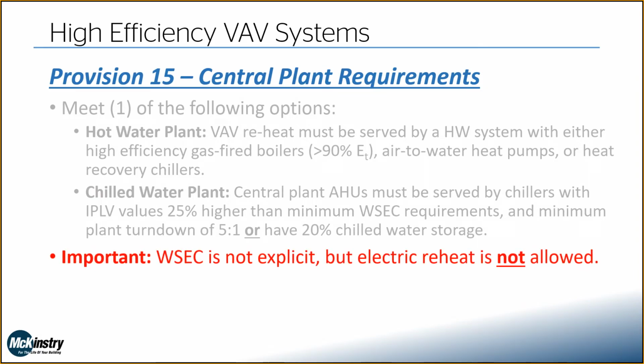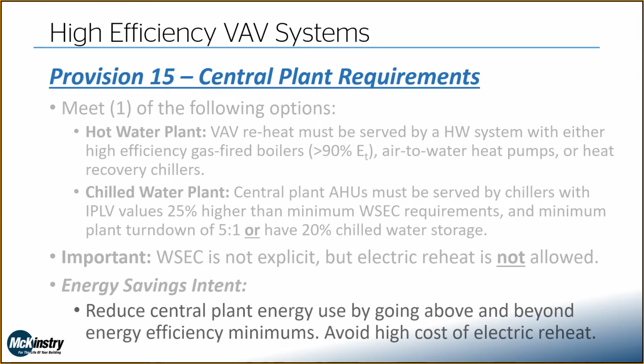An important note here, the code's not explicit, but electric reheat is not allowed. At least this is per the energy code. I forget the team, there's a code technical support team in Seattle, and they say electric reheat does not meet the intent of high efficiency VAV, even though the code is not explicit about that. And that makes sense. I mean, electric reheat is not a very efficient way to do things, considering the alternatives. So just an important thing to note. The intent: let's reduce our central plant energy use by going above and beyond what's actually required by code, and avoid that high cost and high energy use of electric reheat.